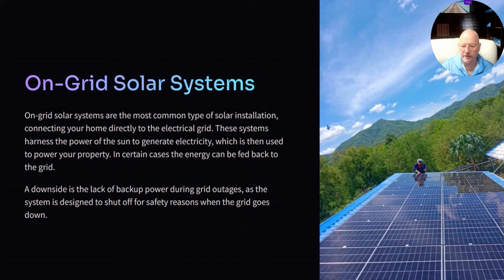And that is because in an on-grid inverter, there is no separate circuit for when you have a power cut. Because you cannot have electricity in a house that's connected to the grid on a circuit that is also on the grid. That doesn't work. If you had that, you could kill workers trying to fix things on the grid. So that's why when we come to battery systems, one of the features of battery systems is that they have a separate circuit that is giving power from the battery, and it's completely separate from the grid when there is a power cut. So that's why on-grid inverters do not give power when there is a power cut. So that's really important to understand.